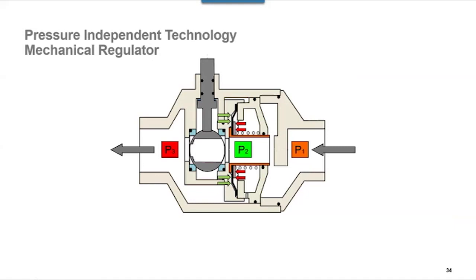The force from P3 pushes the regulator open, P2 pushes it closed, and the whole idea, remember, with pressure-dependent valves, as pressure goes up, flow goes up. Well, in this case, as pressure goes up, the regulator adjusts to compensate. So our output flow is plus or minus 5% due to system pressure fluctuations.